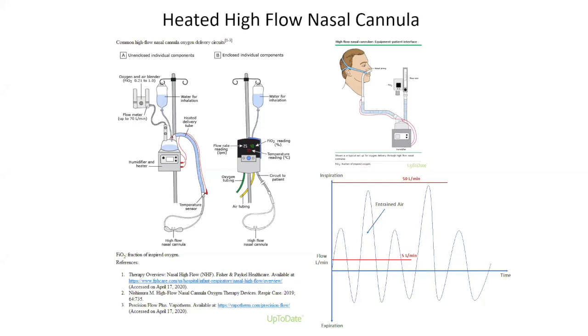But the key here is that there are five parts that are pretty common to this. There's a generator on the top left part that often functions also as a blender. The generator creates the flow, and then the blender mixes the air and oxygen together to precisely set the concentration of oxygen. If you look down at the A setup, you see that there's a humidifier and heater. That's the chamber, and it humidifies and heats the air. That's really critical for high flow nasal cannula, hence the name heated high flow nasal cannula.